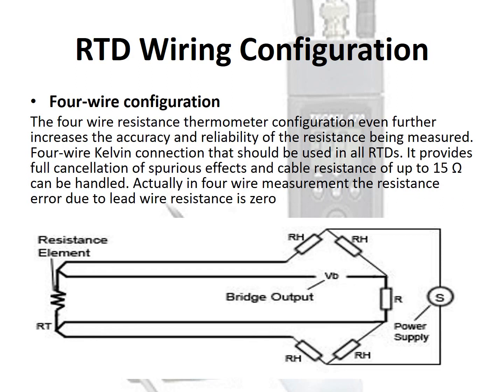The 4-wire resistance thermometer configuration further increases the accuracy and reliability of the resistance being measured. The 4-wire Kelvin connection provides full cancellation of spurious effects, and cable resistance of up to 15 ohms can be handled. In 4-wire measurement, the resistance error due to lead wire resistance is zero.